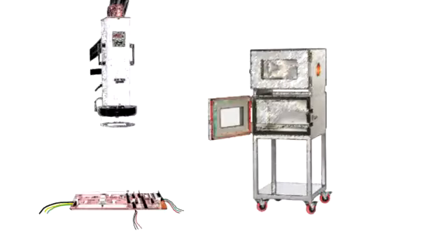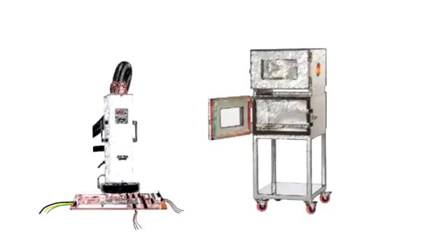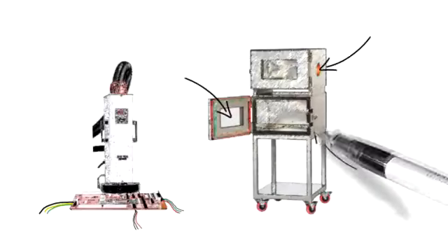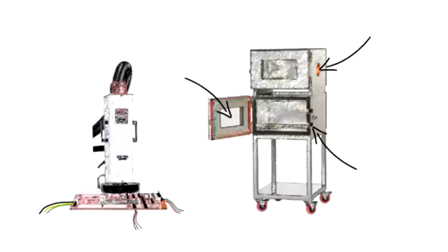And once we know the thermal equation is right, we can improve throughput even more by designing systems that make it easy to load and unload the widgets. Test setups can be complicated, with many cables and connectors. An air forcing system can fit right over the setup. Or a chamber's windows, apertures, and cable notches can make it easy to monitor and access the setup.